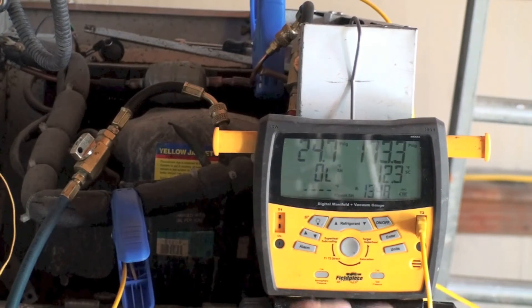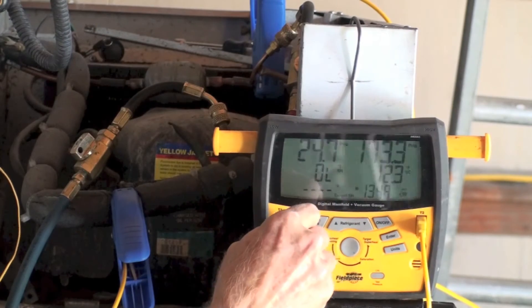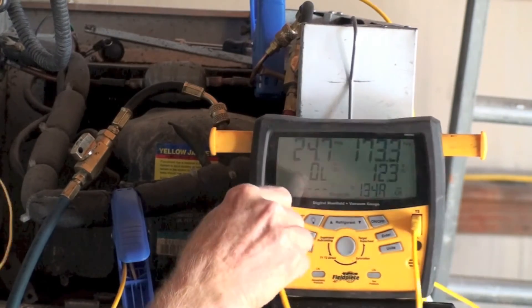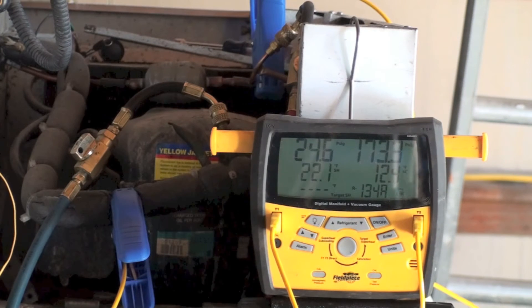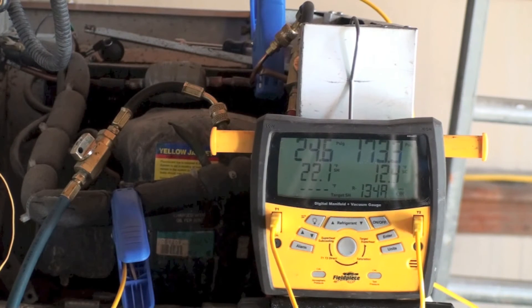Now I've pulled that temperature probe off and I'm using the one on the suction line. Let's see what we've got. Okay, you can see there's a considerable difference between the two.